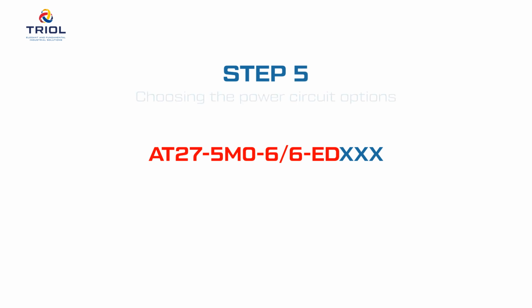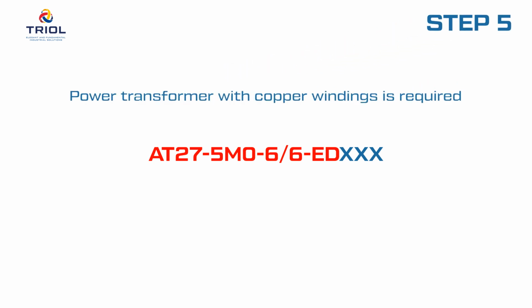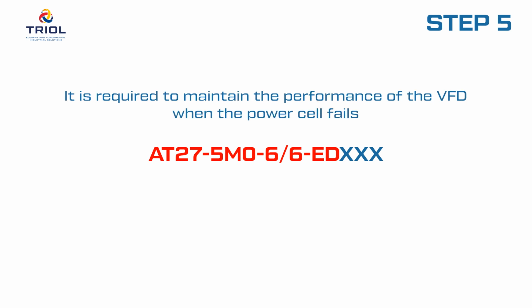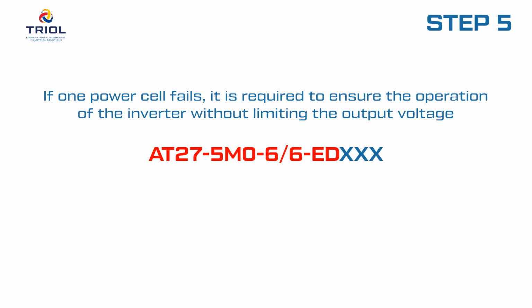Step 5. Choosing the power circuit options. Power transformer with copper windings is required. It is required to maintain the performance of the VFD when the power cell fails. If one power cell fails, it is required to ensure the operation of the inverter without limiting the output voltage. According to the Power Circuit Acceptable Options table, this preset option combination corresponds to the D symbol.